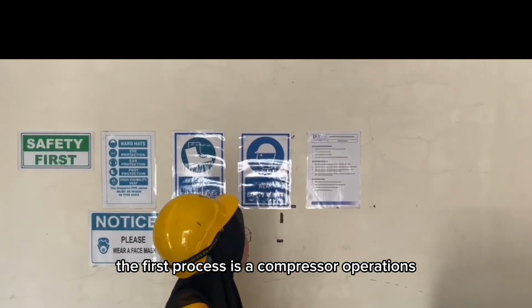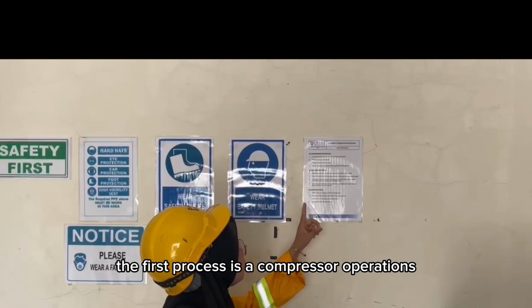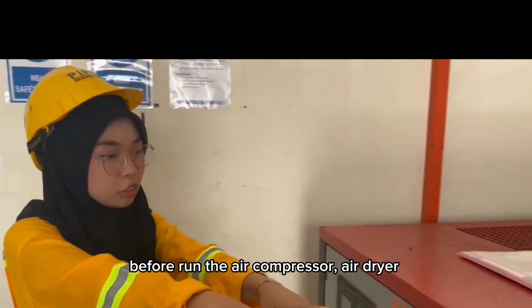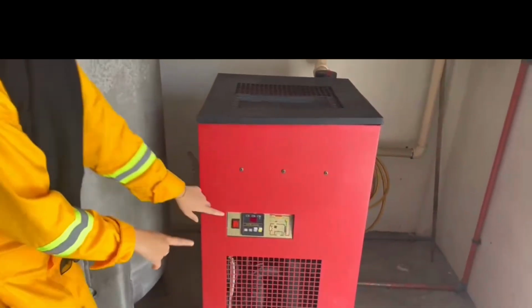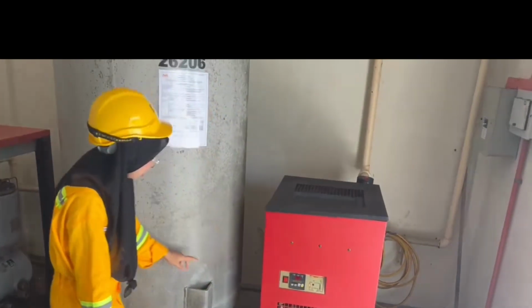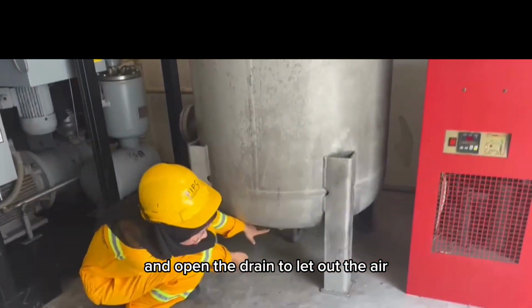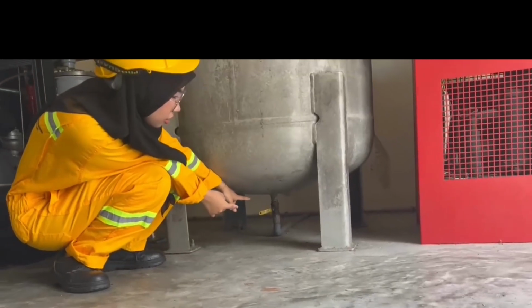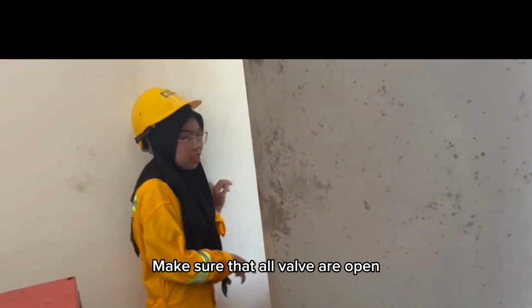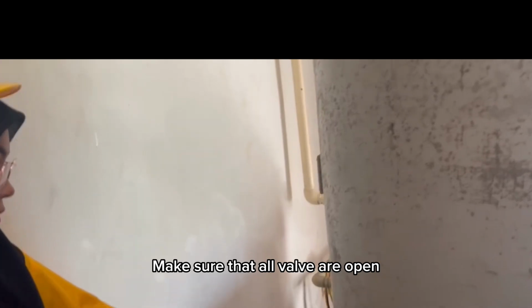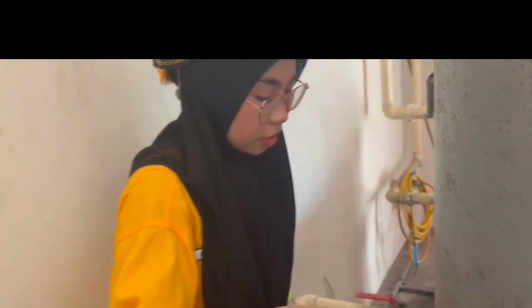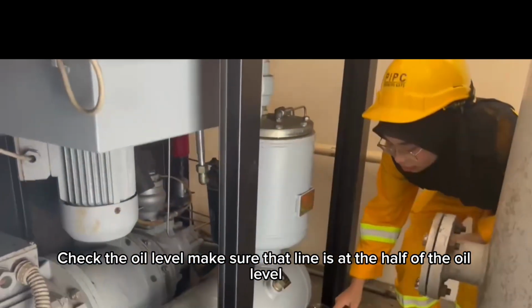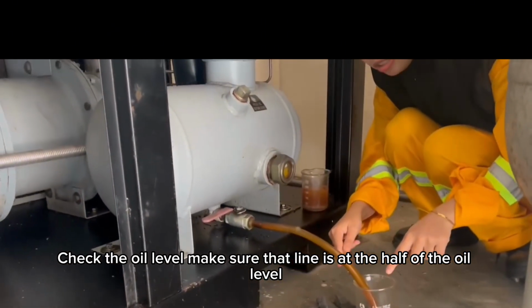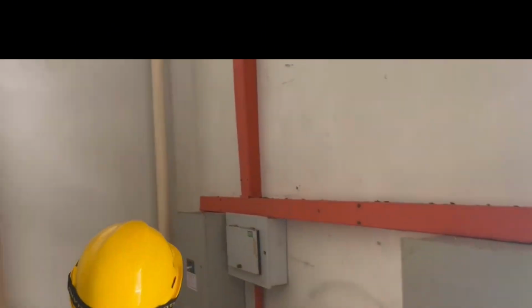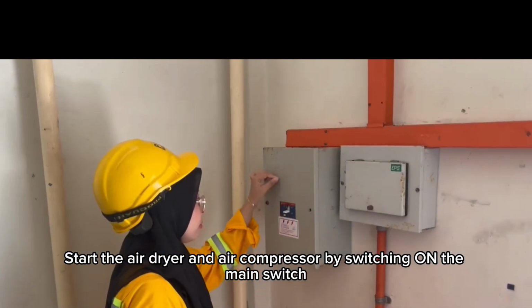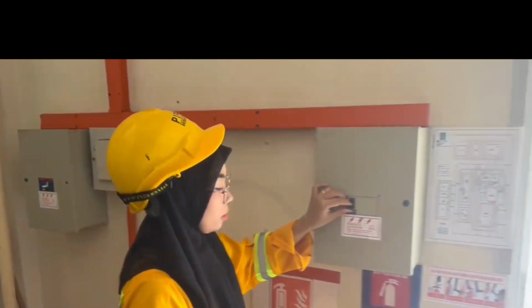So we start. The first process is compressor operation. Before running the air compressor, the air dryer must be started first. And open the drain to let out the air. Make sure that all valves are open. Check the oil level, make sure that the line is at the half of the oil level. Start the air dryer and air compressor by switching on the main switch.